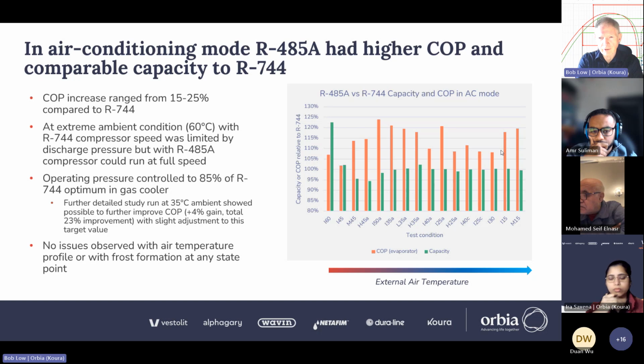The green bars are the actual cooling capacity of the evaporator, and that's the combination of the chiller load and the aircon load. And you can see the green, the lowest it gets is 95% of CO2, but most of the time it's at 100% CO2. Once the ambient drops below 25C, actually the compressor isn't running all the time, and so the capacity would be exactly the same as CO2 because it'd just be cycling to match the load requirements.